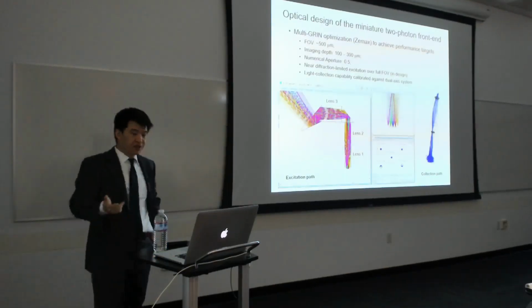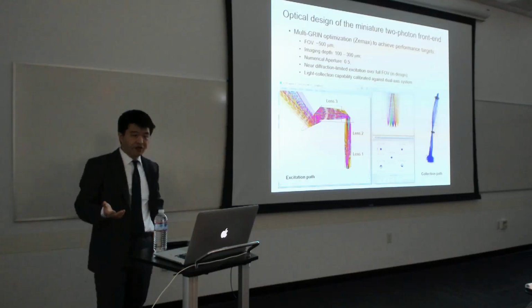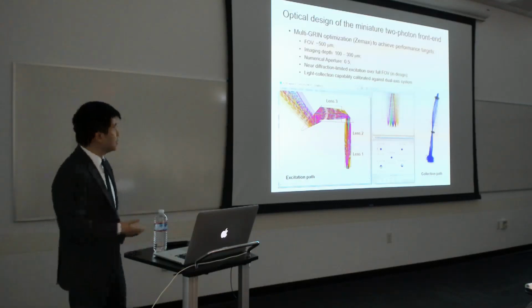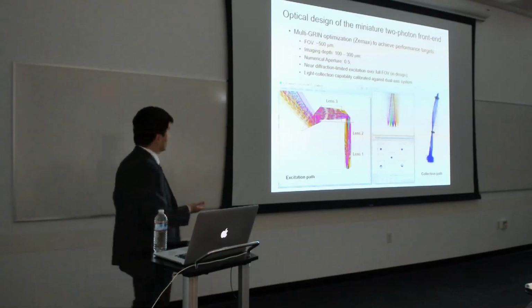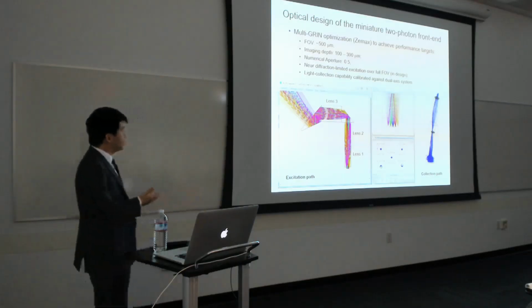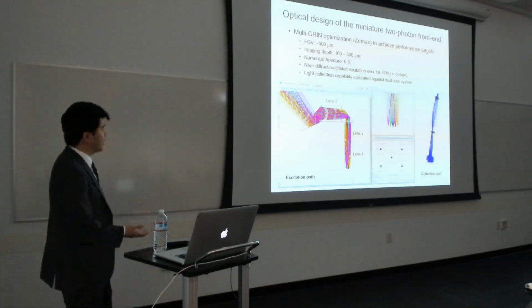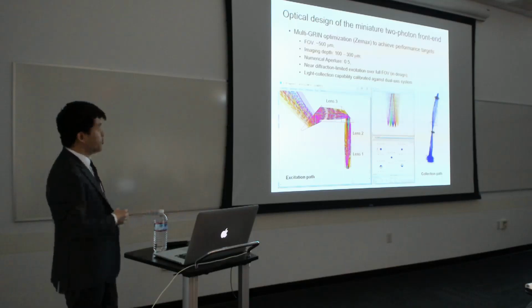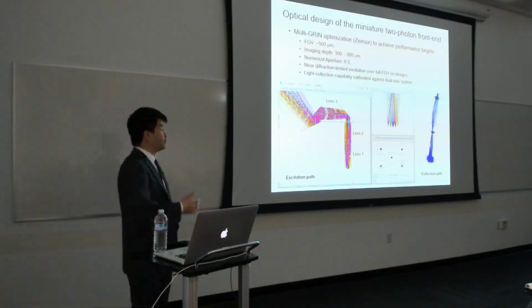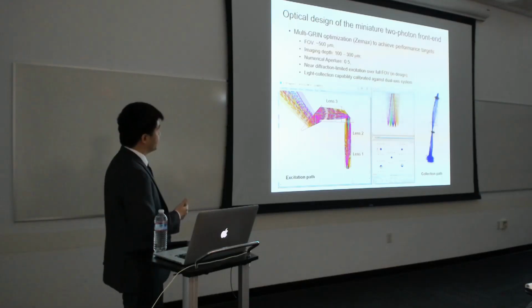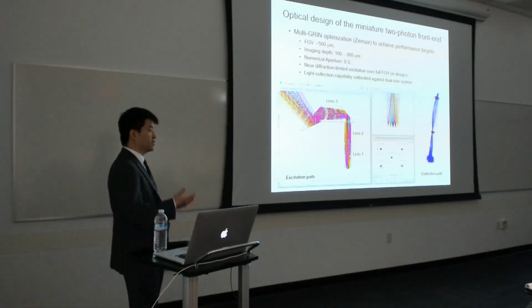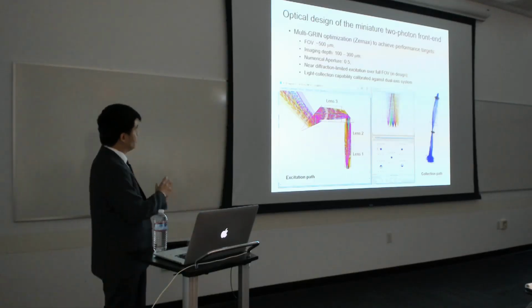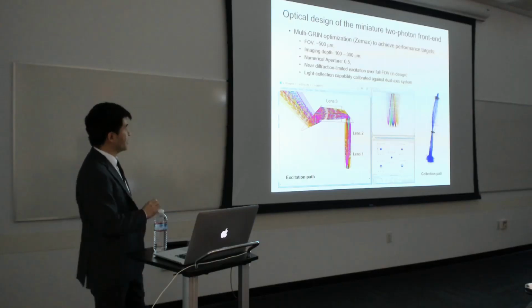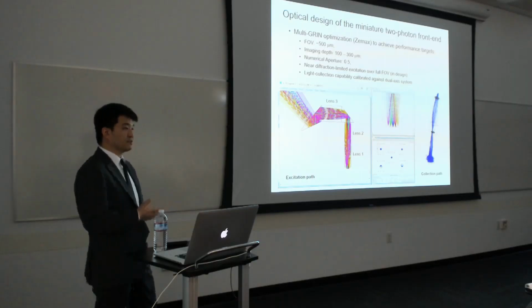As usual in the Schnitzer lab, we use optical simulation to achieve performance targets. Namely, we're aiming for a field of view of about 500 microns at most. We targeted an imaging depth of 100 to 300 microns beyond the probe, and a numerical aperture of 0.5. We were able to achieve near diffraction limited excitation performance over the full field of view, at least in design. And we calibrated the light collection capability against the existing dual axis system.